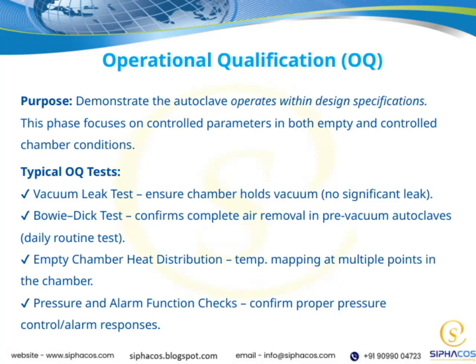Let's take a closer look at Operational Qualification, or OQ, which is a crucial step in ensuring our autoclave functions as intended. The main goal here is to demonstrate that the autoclave operates within its specified design parameters. This phase really focuses on controlling key parameters under different conditions, both when the chamber is empty and when it's in use.